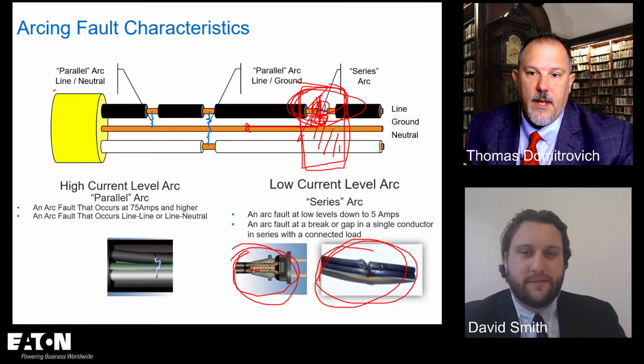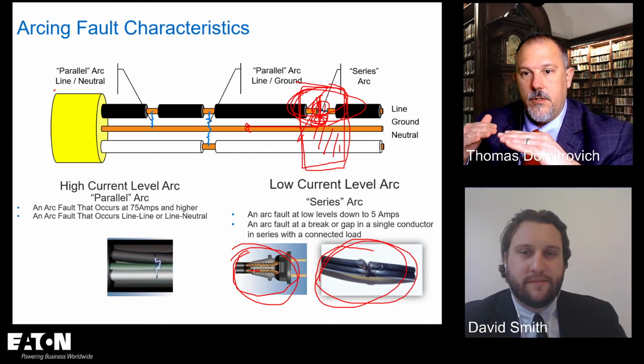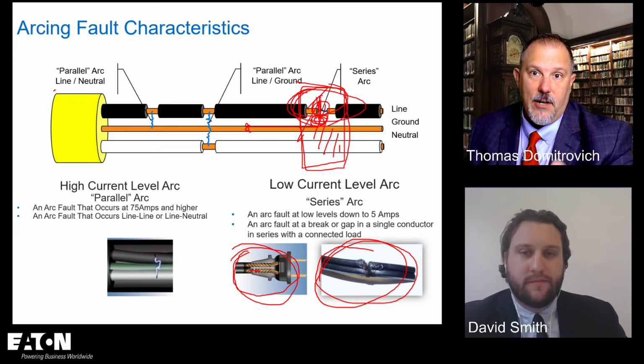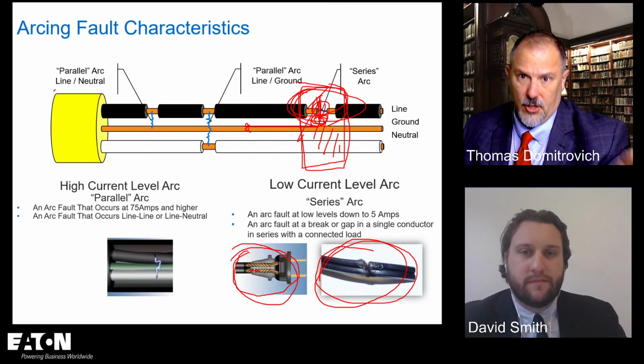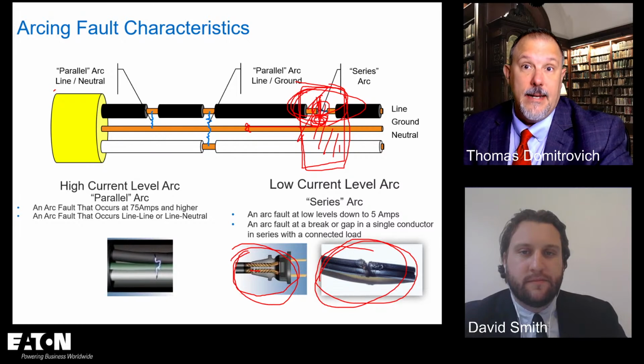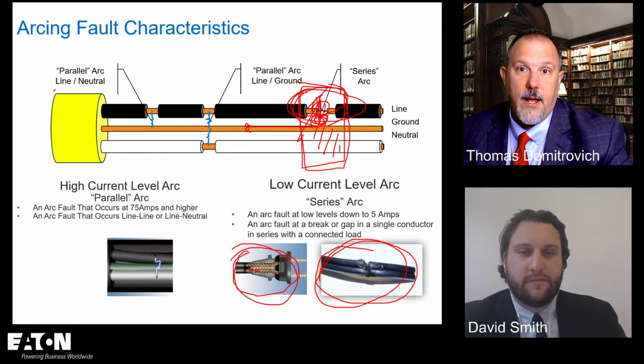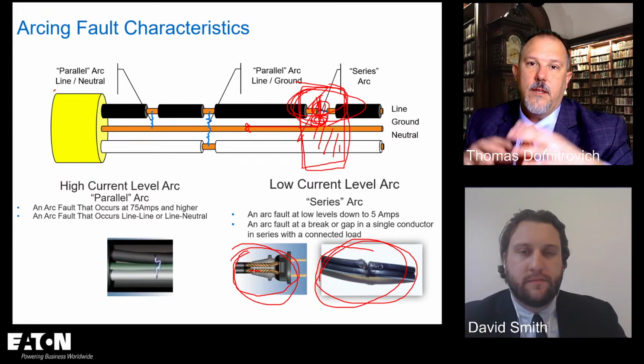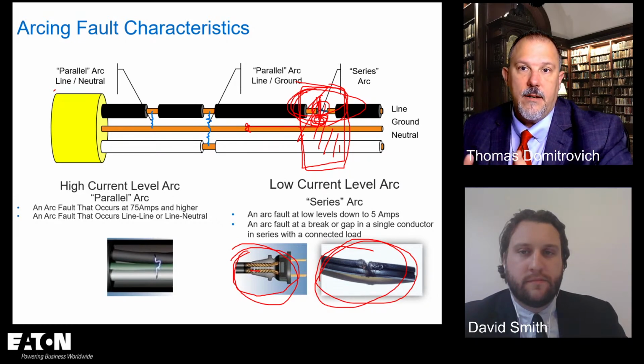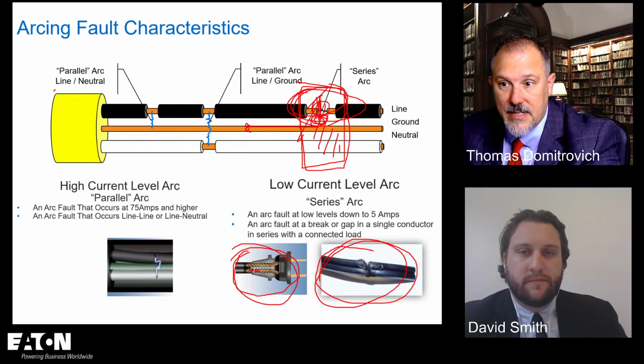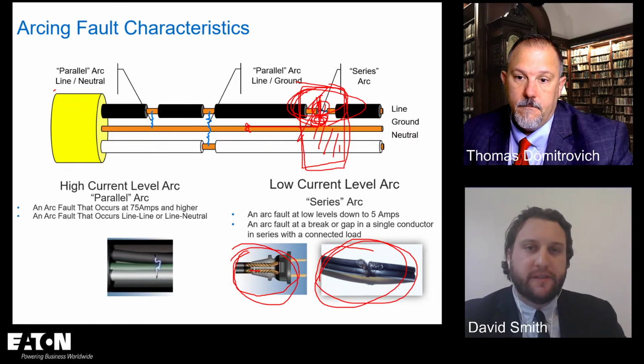the nuisance tripping thing. So think of these as thresholds. If my trigger point is 5 amps, if I took it down and said 1 amp, we could have a debate on whether or not you can start an arc or start a fire at 1 amp, which I have seen done. So I could never say that a fire could not start based on 1 amp. You could, okay? But the standard doesn't have to take into consideration all of that. They've got to be realistic and practical with regard to the compatibility stuff that Kevin's pointing out. Yeah, I guess it's a cost benefit situation, right?